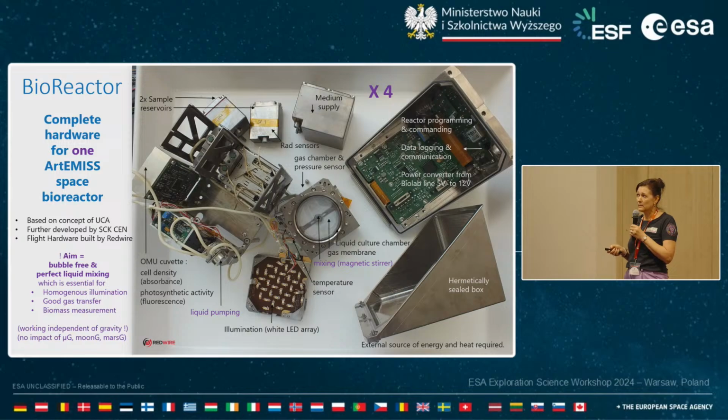Inside it looks like that. It's a very small, or I think still a very small culture chamber, 50 ml. With a polycarbonate window, we have a LED array. Inside we have this white gas permeable membrane. The gas chamber is at the other side of that membrane. On top of the membrane we have a stirrer, a magnetic stirrer bar, but to hold that stirrer during launch vibration, there is this brass bracket and a little cup to hold the stirrer bar.